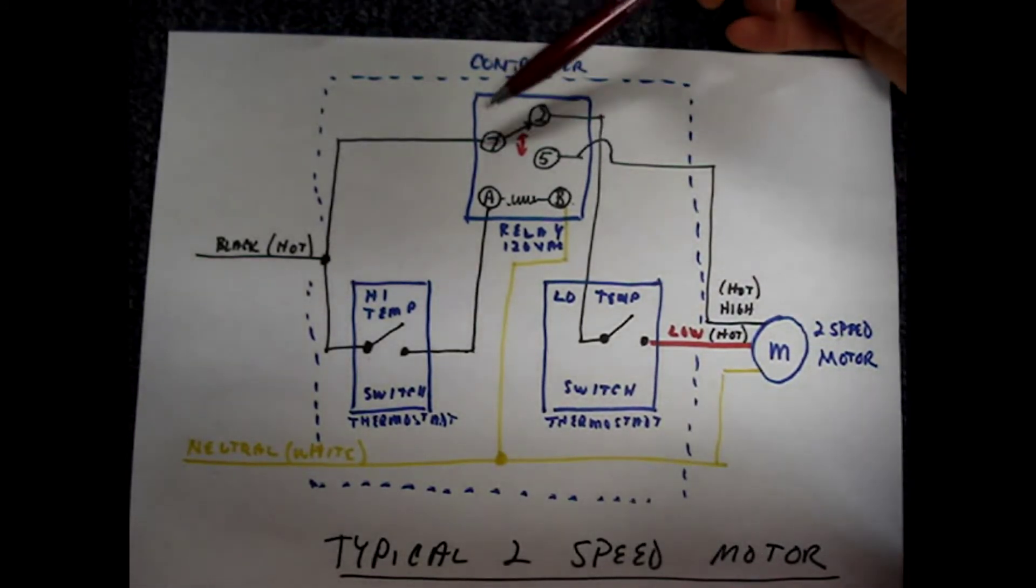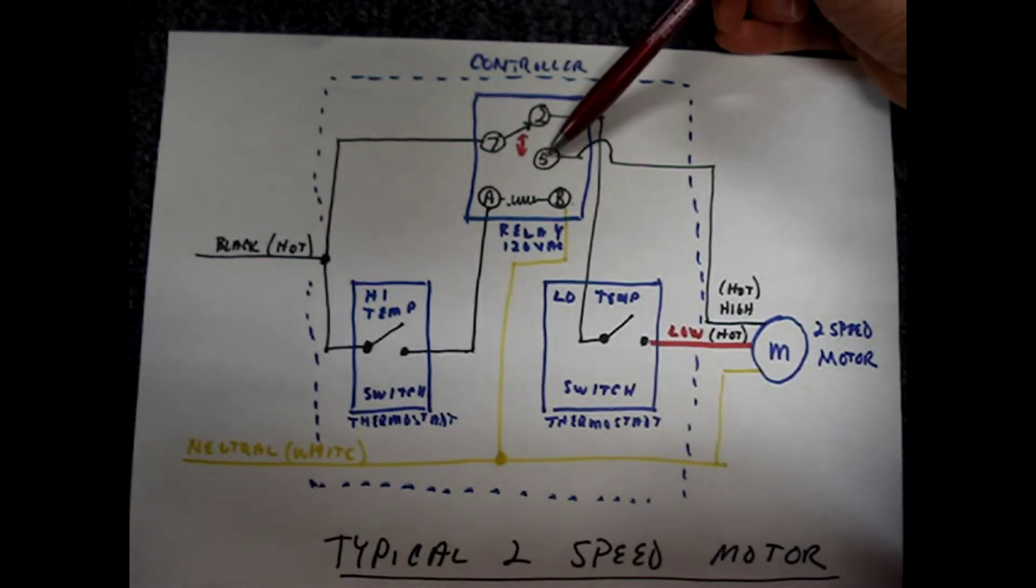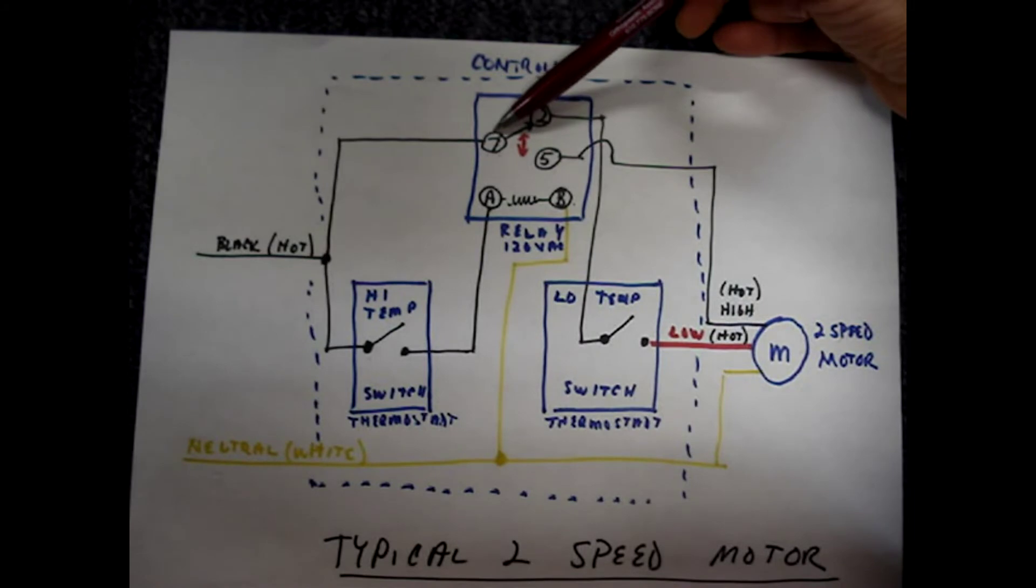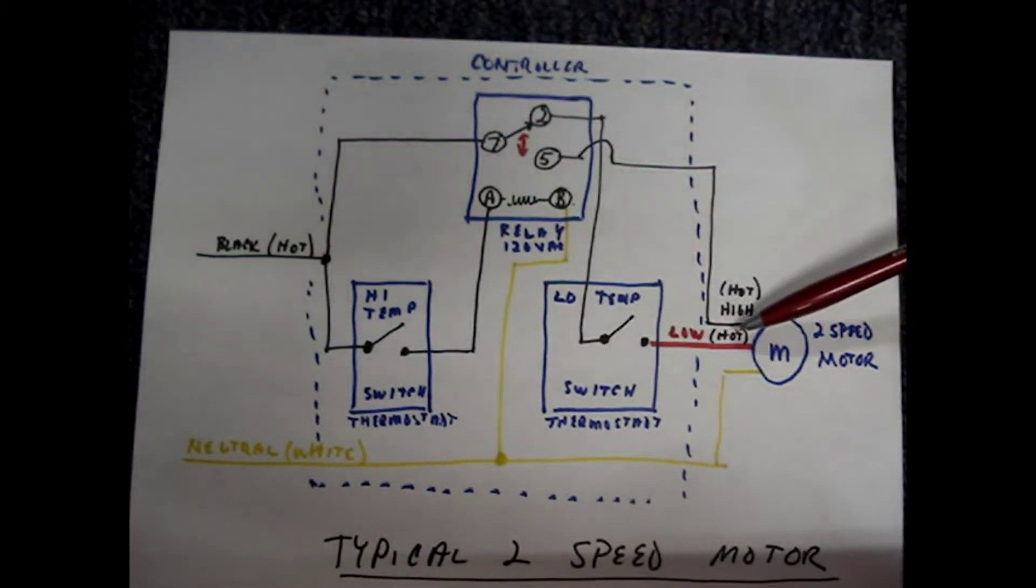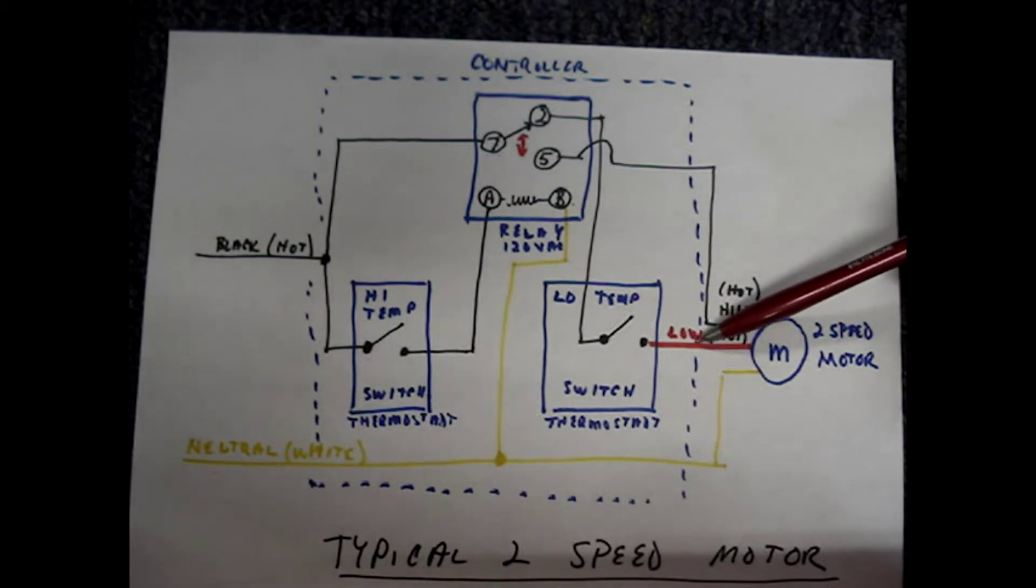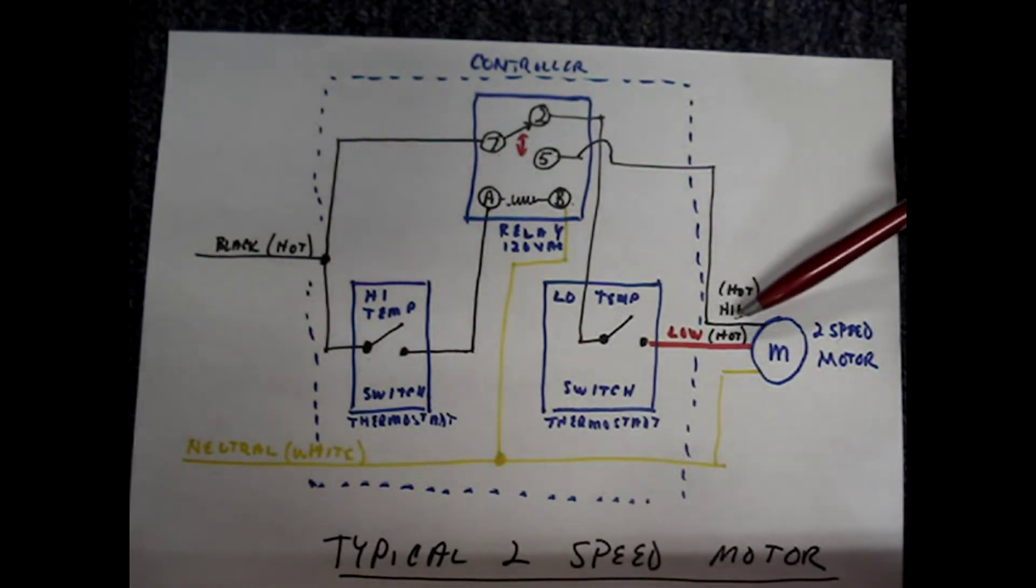Now terminals 7 and 5 are closed and 7 and 2 are open. Power is removed from the windings for low speed on the fan. It's now switched to the high speed windings and the fan runs at high speed.